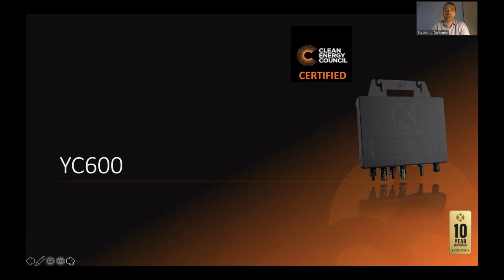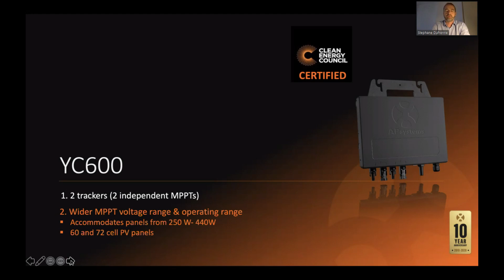Here, let me introduce our two flagship products. Both are CEC certified. First, the Duo single phase, the YC600, with 2 MPPTs. Even though it's one micro for 2 modules, it's really 2 MPPTs, so it's just like having 2 micros together. It has a wider MPPT voltage range, working from 22 volts up to 48 volts. So even at the very beginning of the day, your micro will start producing, and it's typically suited for any kind of module, 60 and 72 cells. The AC output power is 600 watts, and for a micro, it's just like a typical string. You can oversize the panels on the DC side with a ratio of up to 20%.